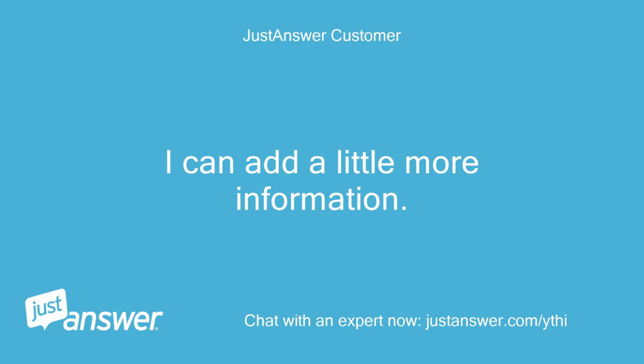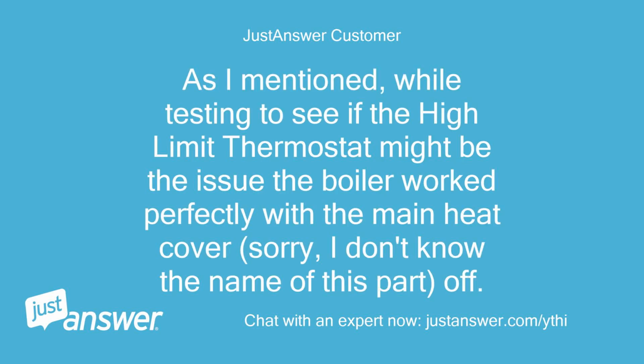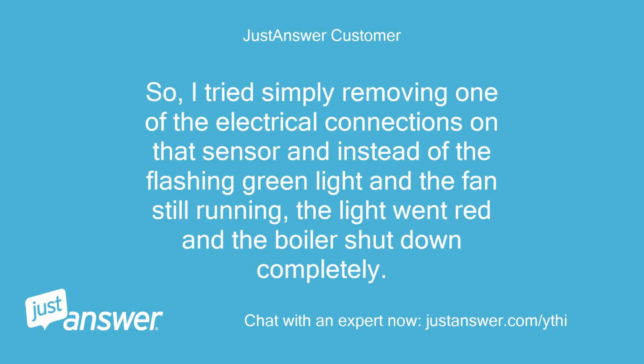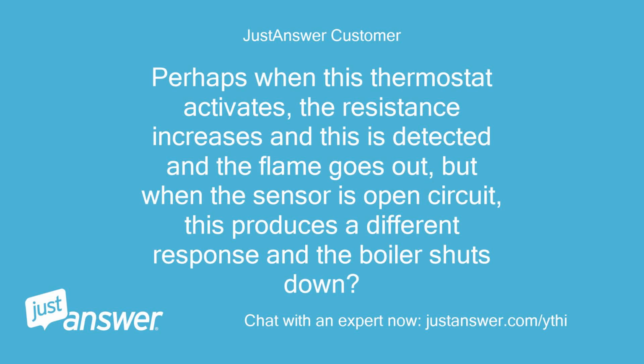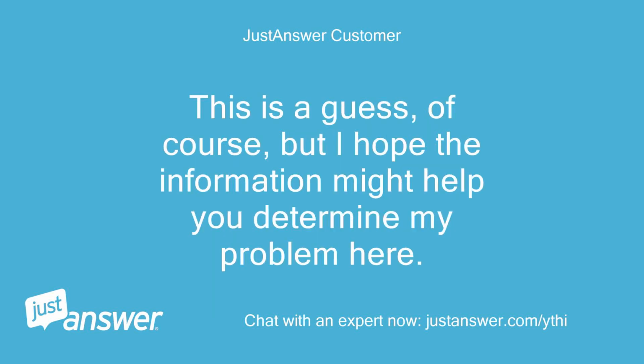I can add a little more information. As I mentioned, while testing to see if the high limit thermostat might be the issue, the boiler worked perfectly with the main heat cover, sorry, I don't know the name of this part, off. So, I tried simply removing one of the electrical connections on that sensor and instead of the flashing green light and the fan still running, the light went red and the boiler shut down completely. Perhaps when this thermostat activates, the resistance increases and this is detected and the flame goes out, but when the sensor is open circuit, this produces a different response and the boiler shuts down. This is a guess, of course, but I hope the information might help you determine my problem here.